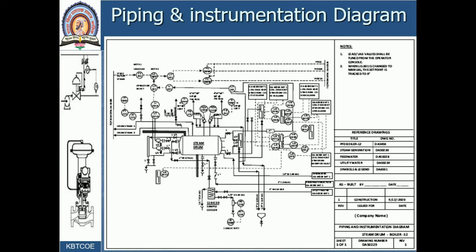The second diagram is the piping and instrumentation diagram, also called process and instrumentation diagram. In the process flow diagram we are not having instrumentation — for example, how you are going to control the temperature of the steam coming out of the boiler is not explained in the PFD. How it gets controlled is not shown. But in the P&ID — the process and instrumentation diagram — we can understand the flow of a process as well as how different process parameters are controlled by different process control loops. So this is somewhat more complex.